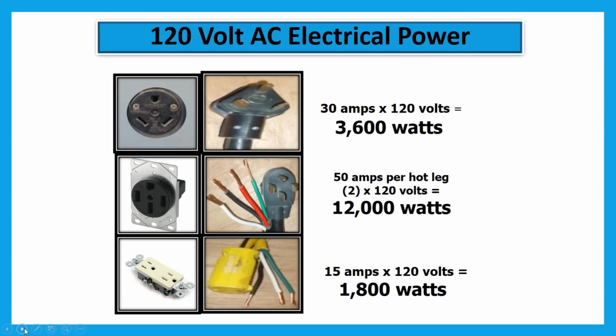Now drop down to the middle row where we're looking at 12,000 watts. Here we have two power legs. One is the black wire, and that's going to give us 50 amps at 120 volts. The red wire is also going to give us 50 amps at 120 volts. And the white wire is going to act as a return path for those electrons.